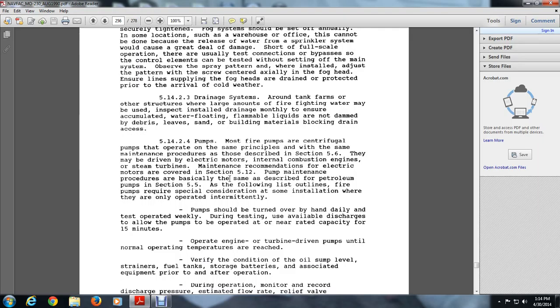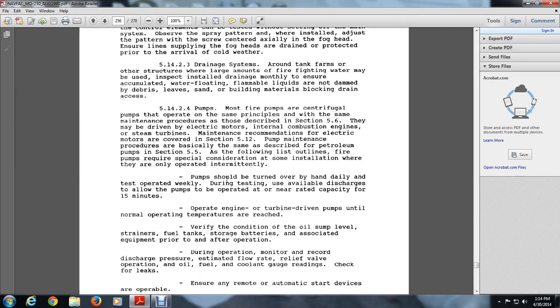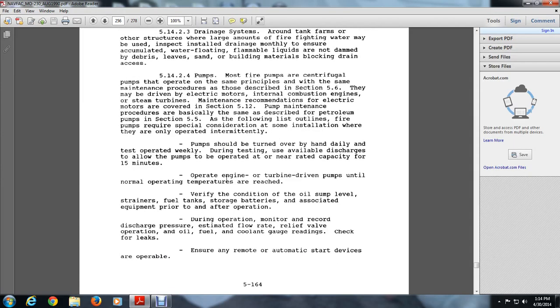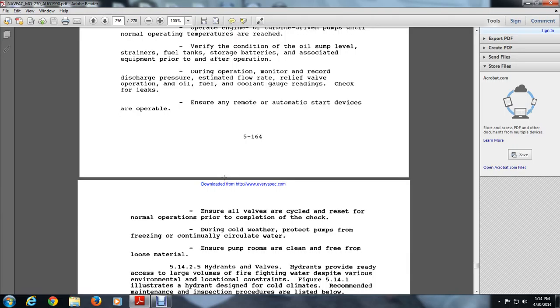and after the operation. During the operation, monitor and record discharge pressure, estimated flow rate, relief operation, and oil, fuel, and coolant gauge readings, checking for leaks. Ensure the remote and automatic start devices are operable. Ensure all valves are cycled and reset to normal operation prior to completion of the check.